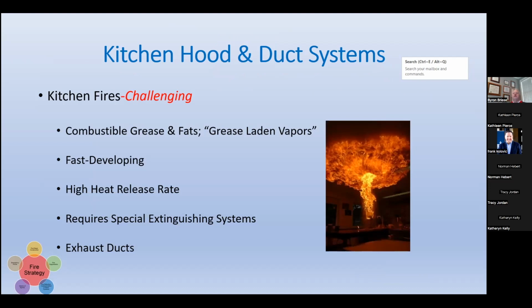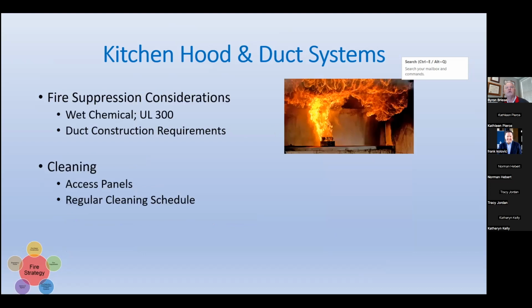Let's get back to those kitchen hoods and duct systems. We have combustible greases and fats. Industry changed out the grease style in the late 90s, so we ended up with a new standard, new at that time but now a couple of decades old, called UL 300. If your extinguishing system meets that standard, which all should at this point, though I run across some occasionally that don't, you should be in pretty good shape in the event of an incident. That said, you still have to do good maintenance on the system, clean your exhaust ducts, and train your folks in the use of all of that equipment.